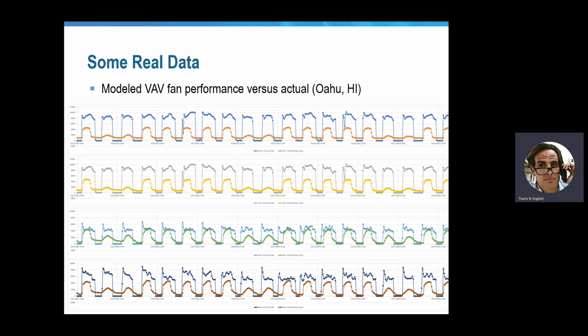The third thing to look at is the spike that you see every morning on every air handler. That spike is not a mistake. It is part of the design. That's the morning warm-up sequence. It's on the plans, it's in the specs, it is 100% part of the design. It is 100% not part of the energy model. And so that's inaccurate. If we're going to have a spike every morning in the design, we should have a spike every morning in our calculation. It's going to do that 260 mornings per year, by the way. That's 260 hours per year that will be at full power. That's like adding an extra month to the fan power.